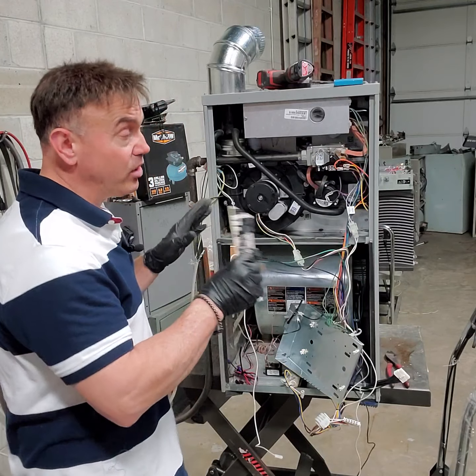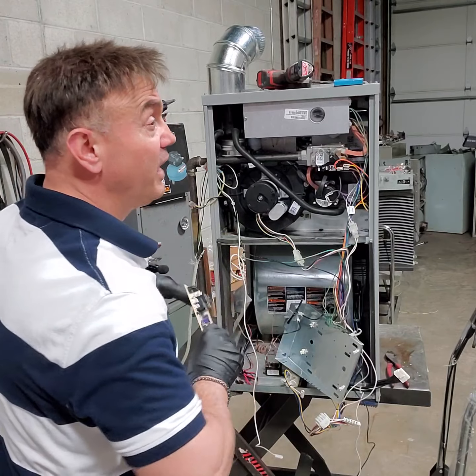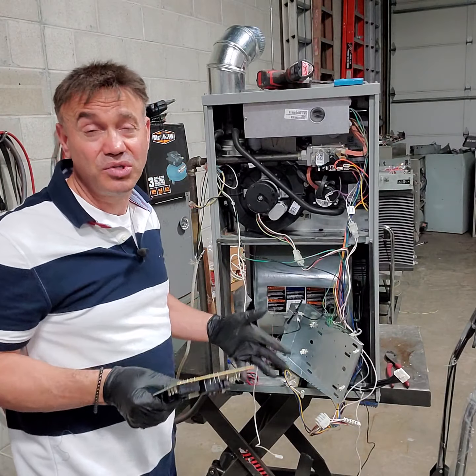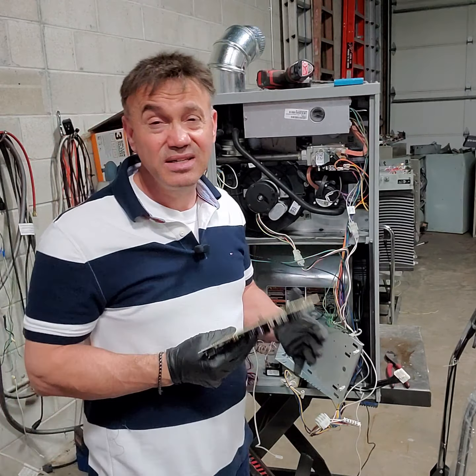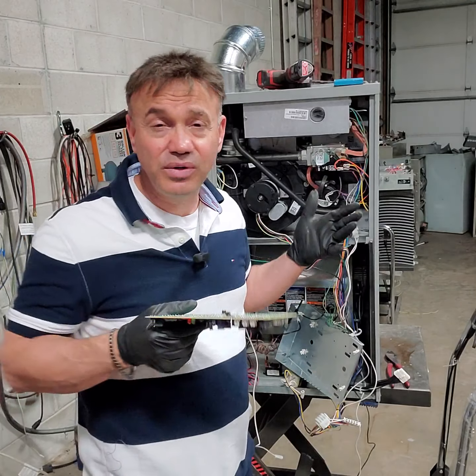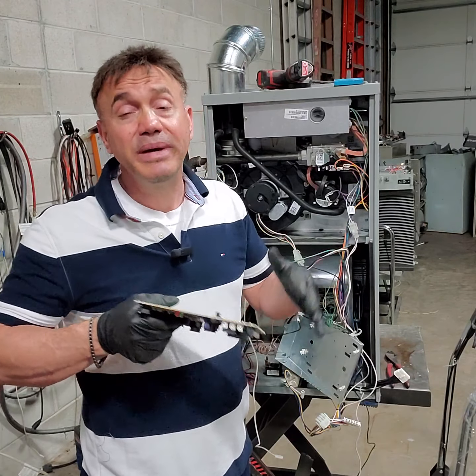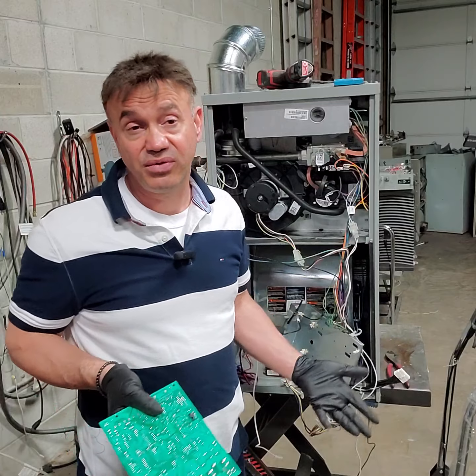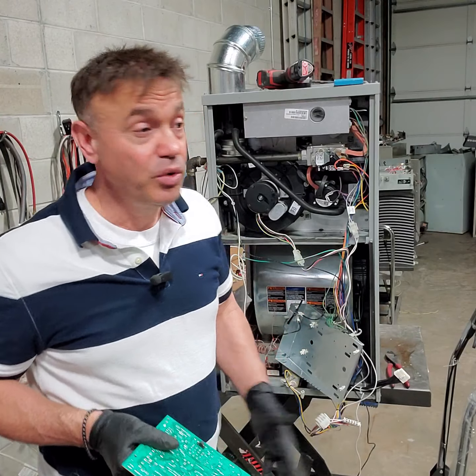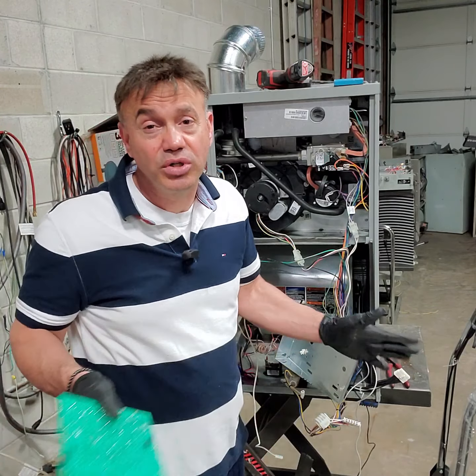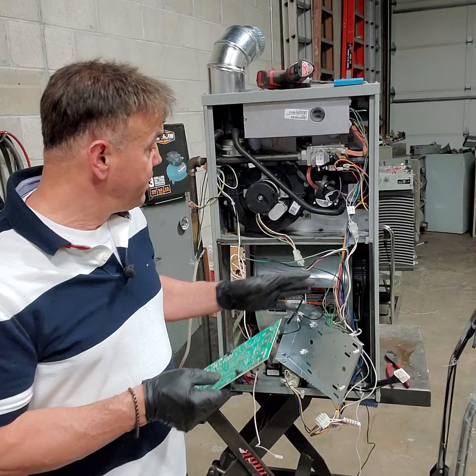If you have a bungalow house, you put the furnace in the middle and go both ways. With new construction I always do that, because no matter how much return you give the furnace, you cannot go too big with the return. The return is always good for the furnace, it loves a big return. You can have 3 returns and it will never hurt.